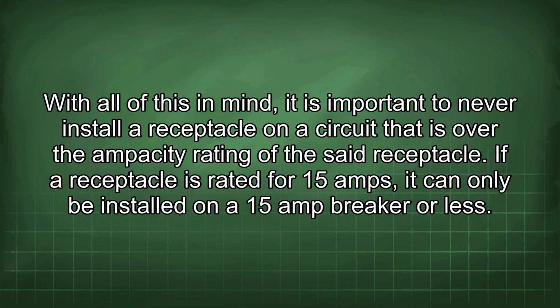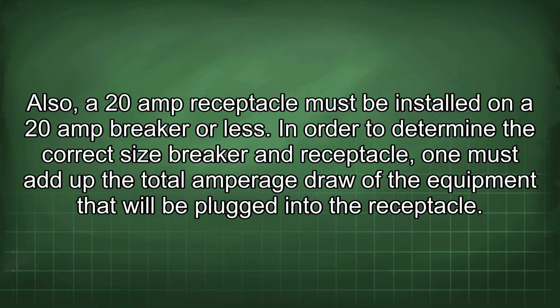With all of this in mind, it is important to never install a receptacle on a circuit that is over the ampacity rating of the receptacle. If a receptacle is rated for 15 amps, it can only be installed on a 15-amp breaker or less. Also, a 20-amp receptacle must be installed on a 20-amp breaker or less.